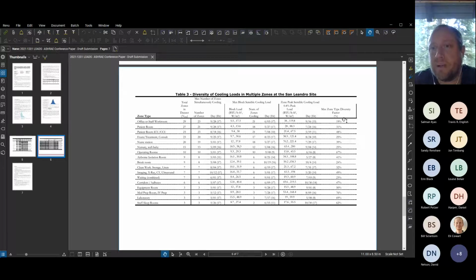At the far right, you can start to see when we actually calculate the block load that we saw at that peak hour, we calculate that against a design load, and you can get a sense on the far right of what sort of a diversity factor shows up at that time. So when we had, just as an example, 27 patient rooms in 2020, at the hour where we saw the maximum block load, only 18 zones were in cooling, and the actual load that we saw relative to the design load was only 31% of what the peak would be if we summed up the peaks for each of those rooms.